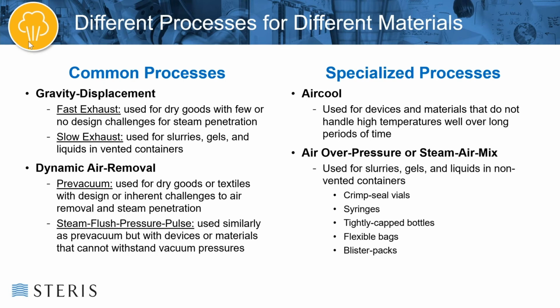And then we have a couple of specialized processes. There's one called an air-cool cycle, which is very similar to a gravity displacement slow exhaust cycle. But during the air-cool cycle, the steam is removed from the chamber and is replaced with pressurized air. And the steam in the jacket that we saw in the previous slide is removed and replaced with cold water. This process is designed to cool the items in the chamber faster, for items that are somewhat heat labile and are not able to remain at high temperatures for long periods of time. And then another one of these specialized processes is air overpressure, sometimes called steam air mix.